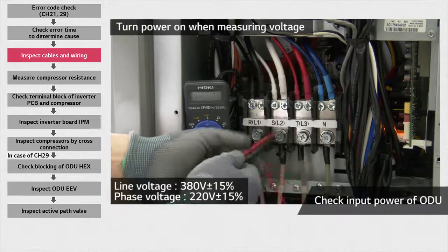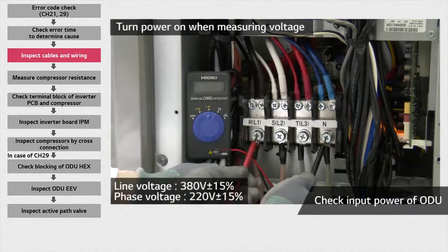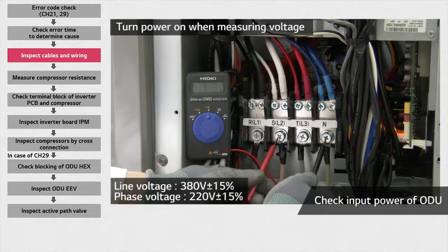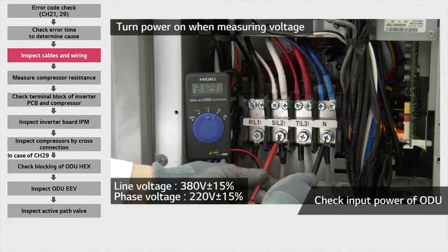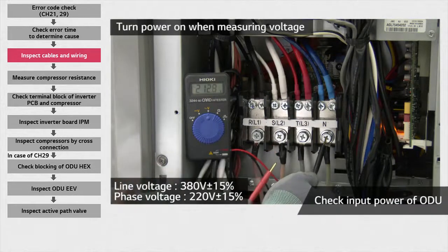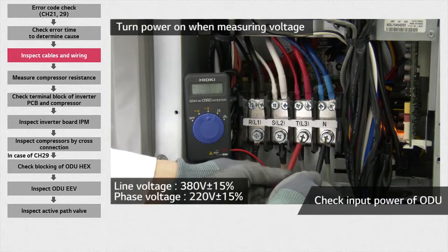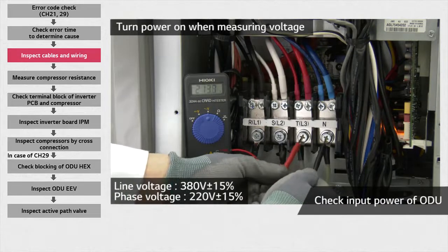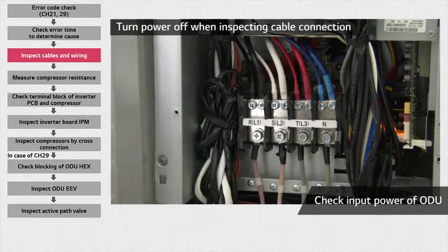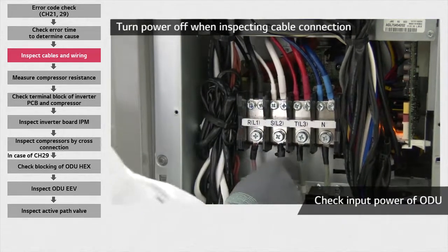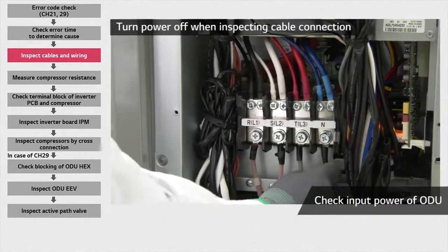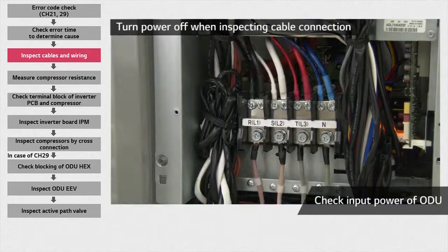Check if the wires are tightly connected. Now, check the condition and wiring of the RS-TN cables. Check that the power is normally supplied to the outdoor unit, and then measure the voltage between phases. RS, RT, ST are the line voltage. If the voltage is not normal, the problem could be in the circuit breaker or in the cables. Proceed to check them as follows.